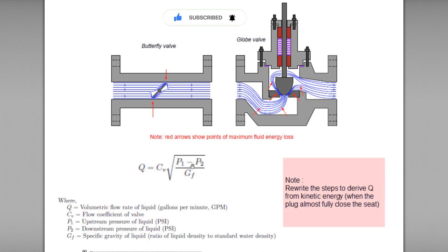This is a formula for the volumetric flow rate of the liquid. Q stands for volumetric flow rate of liquid in gallons per minute unit. P1 minus P2 is differential pressure where P1 stands for upstream pressure of liquid in psi. P2 is the downstream pressure of liquid in psi. While GF is a specific gravity of liquid which is the ratio or division between the liquid density to standard water density.